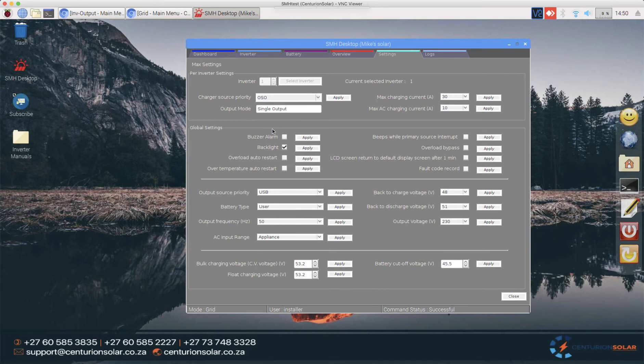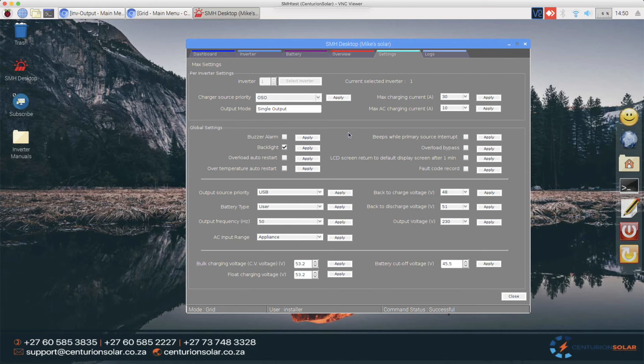Now I can also go and change the global settings. These settings would affect both, or three, or four, however many inverters you have in your setup. For parallel setups this is common to all of them. For argument's sake, you can't have one system running 53.2 volts bulk charging voltage and the next one having 54 volts, it simply doesn't work.